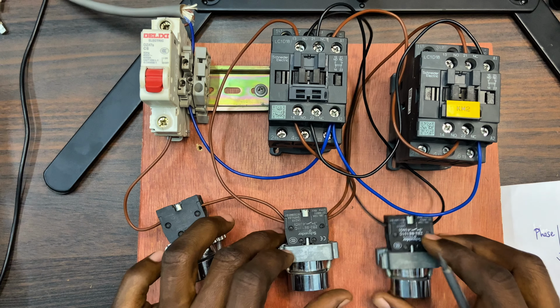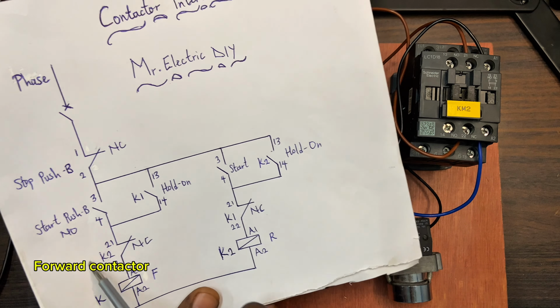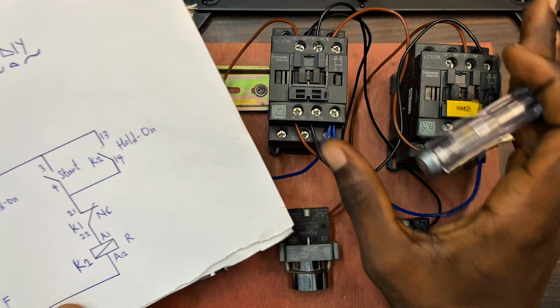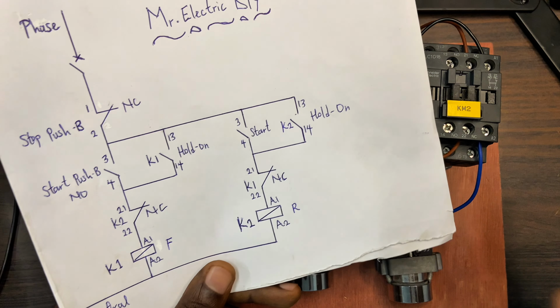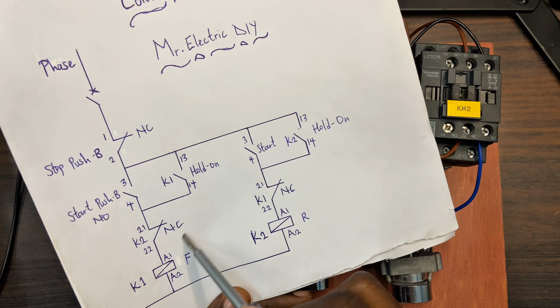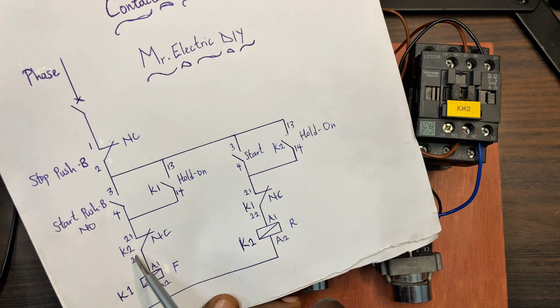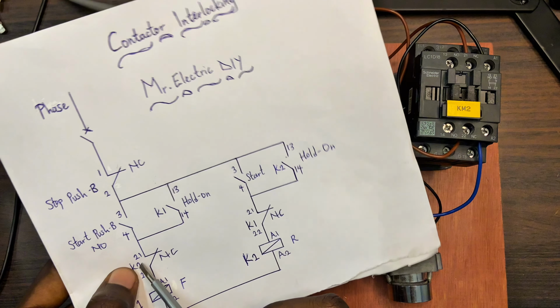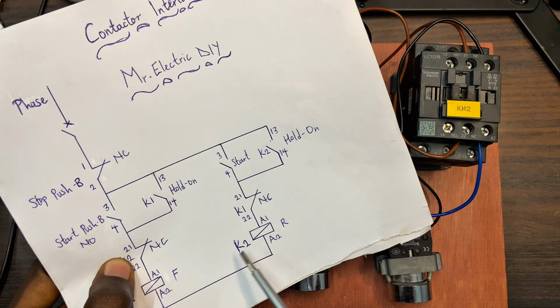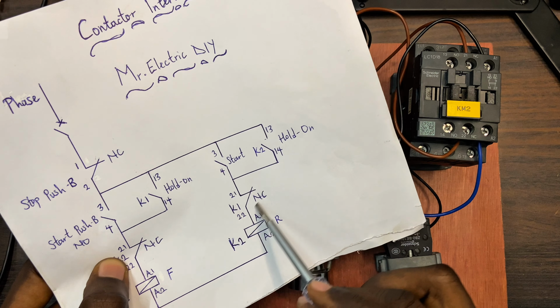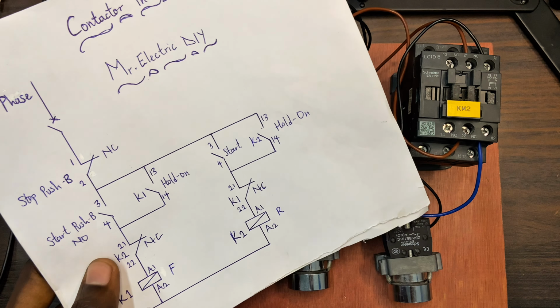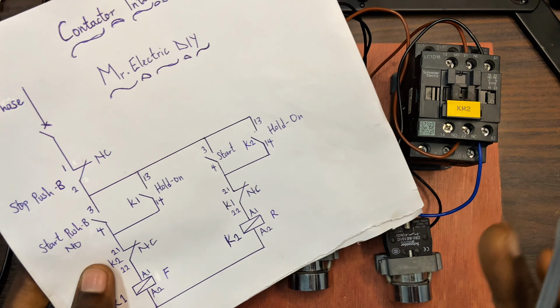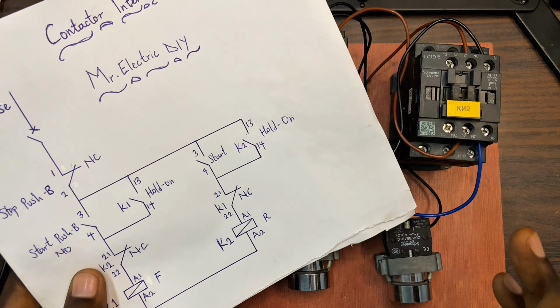Guys, we are done with the interlocking. It has left with the hold on. We have interlocking between the forward contactor and the reverse contactor. That is the electrical interlocking, interconnection between the two contactors, the forward and the reverse. So right now we have this normally close found on the reverse contactor. That is K2. Now the normally close found on the reverse contactor. And this is normally close. This normally close you see here can be found on the forward contactor. That is K1. So guys, that is how to do interlocking. Now, without the hold on, let's operate the circuit.